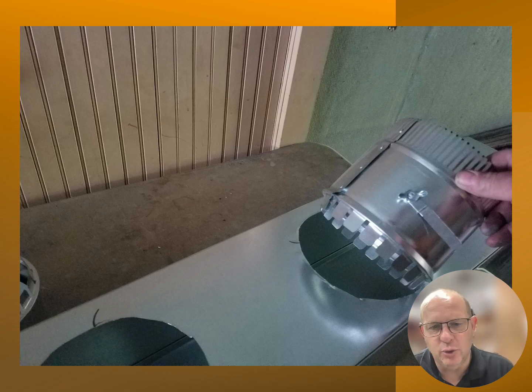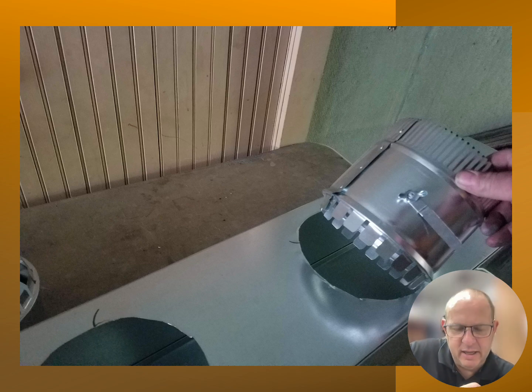Sometimes I will even use a hammer to hammer those tabs into place so that I got a nice tight connection on it that's not going to move around. It doesn't matter after I put the mastic on it anyway, and that mastic sets up. It is a tight seal once that happens, but this is the way that you install a damper with a takeoff, with a damper inside of a branch ductwork, inside of a main trunk as we're going down through the system.